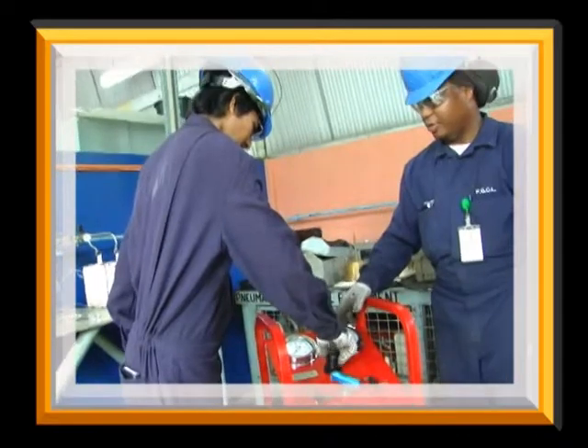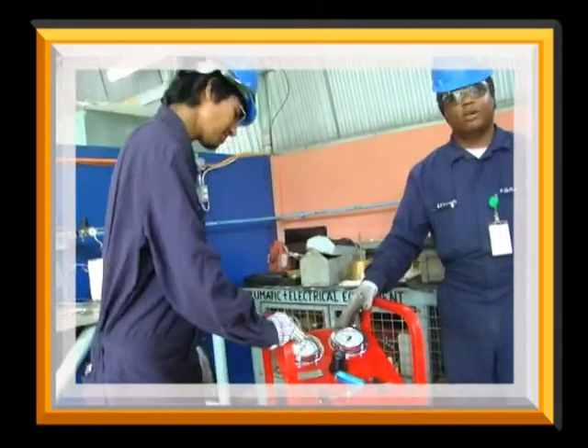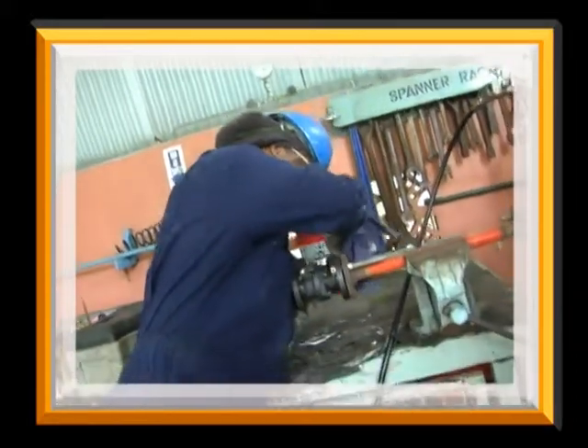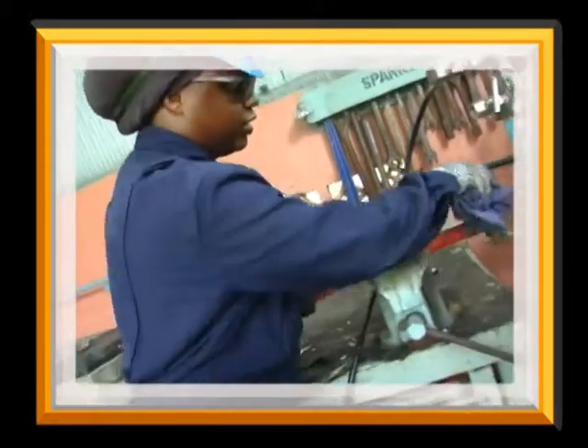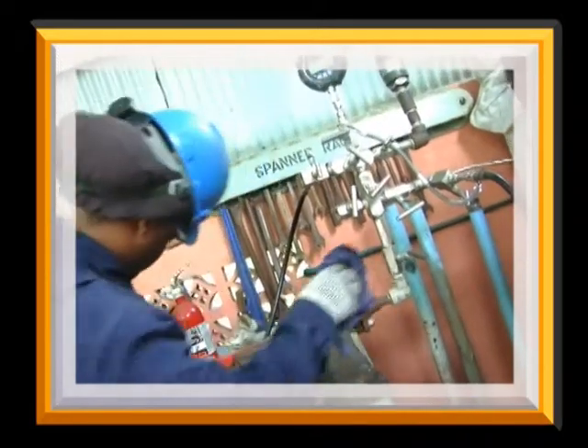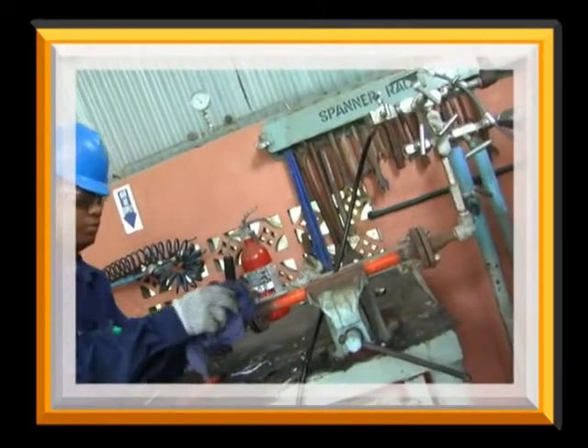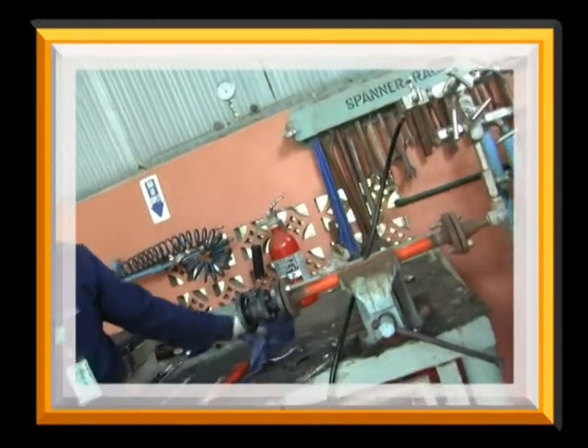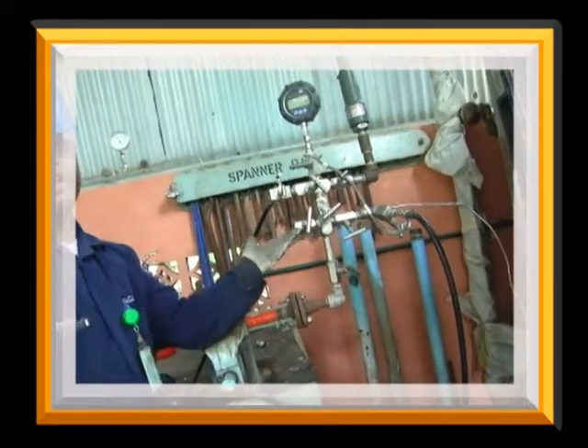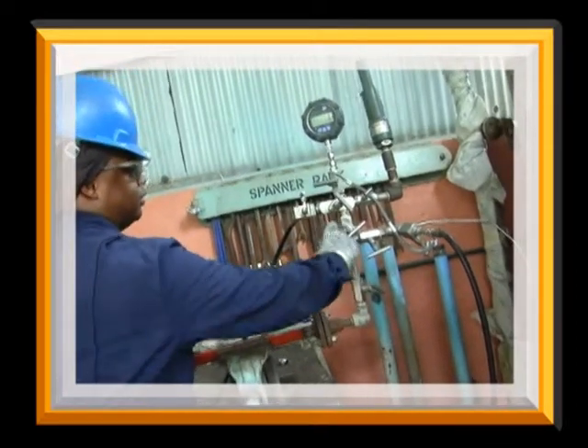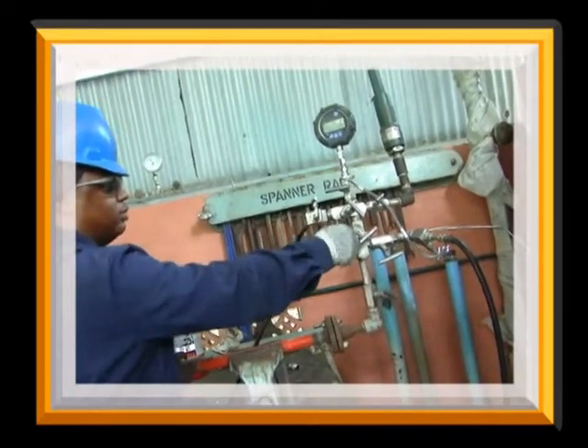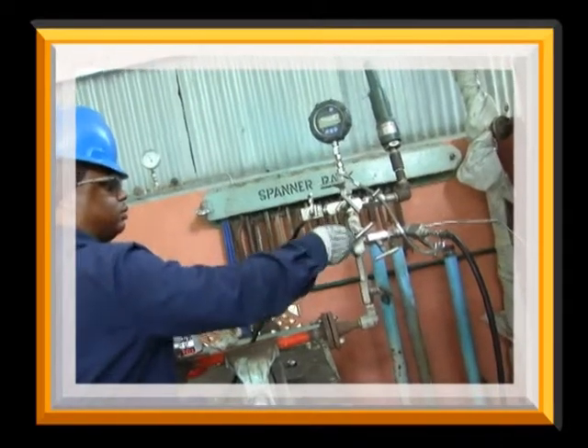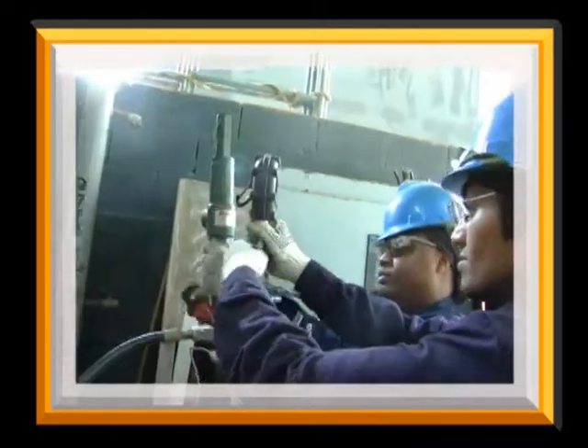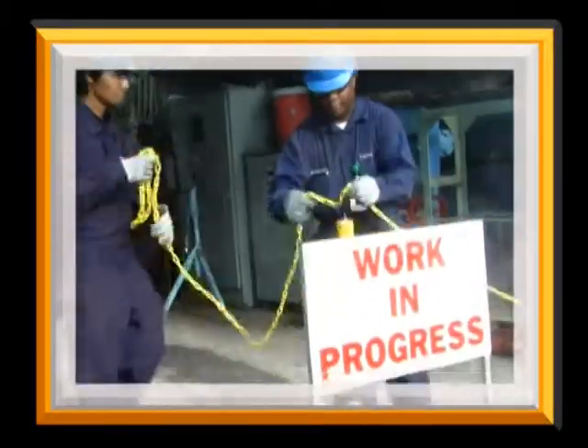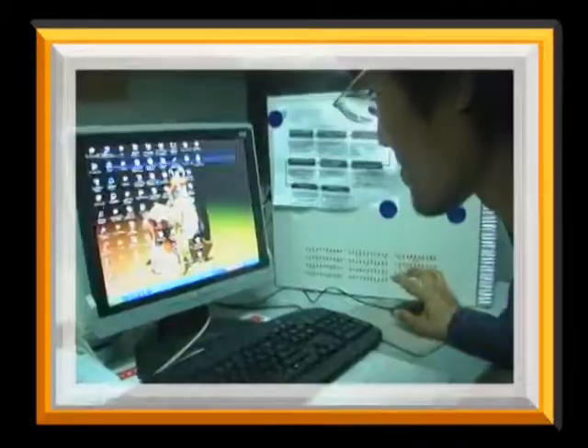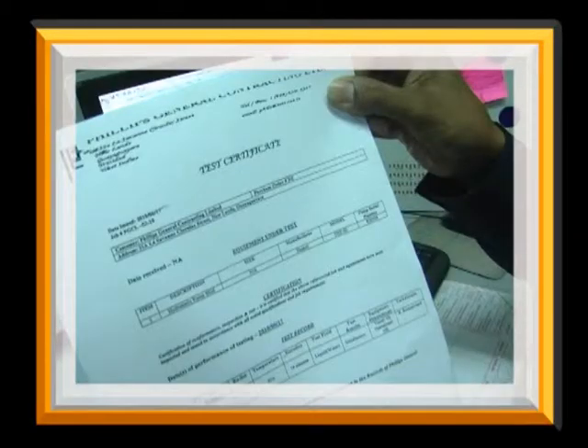The final test pressure is held for at least 30 minutes with no visible leaks to atmosphere before a detailed inspection is started. The test item is inspected for leaks. After satisfactory completion of the leak test, there is a gradual release of pressure and drain down. Test systems should be depressurized by opening required vents and valves. On completion of the test, pressure connections, barriers, and warning signs are removed. A digital gauge report as well as certificates are printed and packaged for the customer.